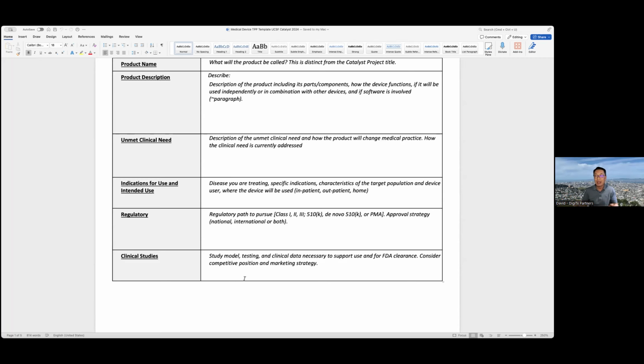So depending on the level of intelligence that it has and level of invasiveness. Going specifically to the medical device area, if it's something that's implantable, it's going to be a PMA. And it is a long process. So you have to put that into consideration, because anything that's going to be implanted will require animal work. Potentially you may start with small animals, then large animals, because you have to have wear data. And then you will have to have clinical information, clinical validation before you get to even the FDA process.